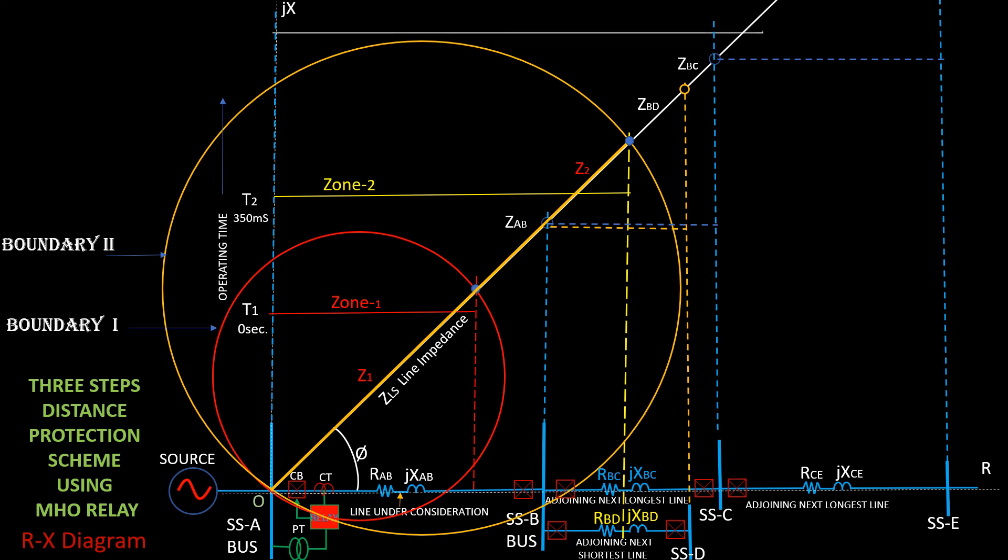Zone 3 protects 100% of the line between substation A and substation B plus 100% of the line between substation B and substation C plus 20% of next adjoining line.